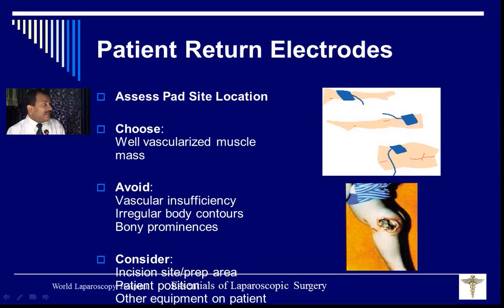You should avoid irregular body contours. Sometimes when you are doing the vaginal part of a hysterectomy, the patient's buttock was not up to the edge of the table, and there was a patient return plate which you had applied here. Then you ask your assistant to pull the patient, and suddenly the return plate is displaced into the hollow of the sacral curve. Now that narrow area comes into contact, and immediately that area will burn.